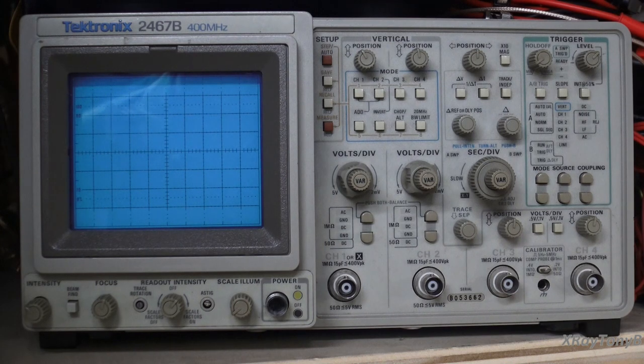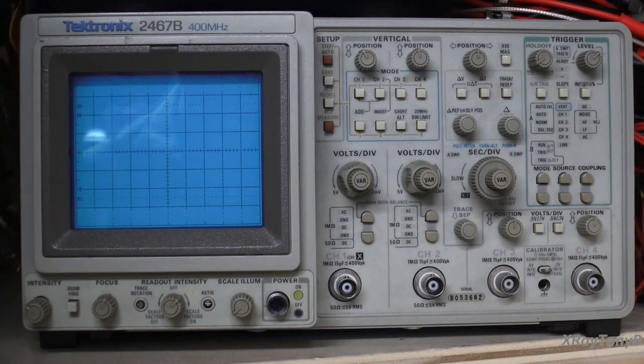So if you're working on an electronic piece of equipment, make sure it's plugged into an isolation transformer. Make sure that it's battery operated. Make sure that the chassis ground or your ground reference that you're going to measure is at the same ground point as your ground prong for your AC mains plug. Now, a lot of equipment today is grounded and always referenced to ground, but there's stuff out there that's not. It has what's called a floating ground, and if you have a floating ground and you connect this up, you're going to be in trouble. And you don't want to damage your very expensive probe, your very expensive scope, or your priceless you by not being safe. So that's a word of warning right there, and you need to remember that.